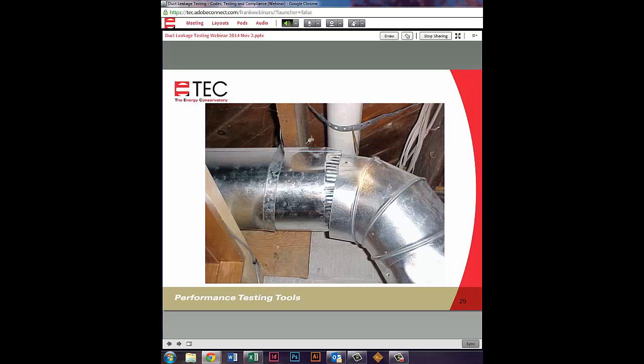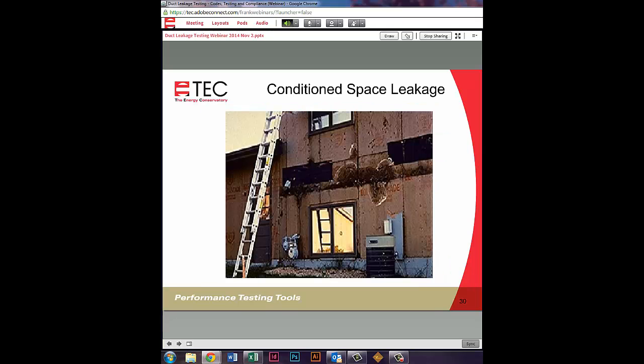This contractor, I think, probably should get an A for effort, but certainly an F for execution. It's pretty clear that he was trying to fit the ductwork through the cavity on the left-hand side, but the plumbing pipe on top just wouldn't allow him to make the connection of the ductwork on the right-hand side. So it's close, but not really good enough.